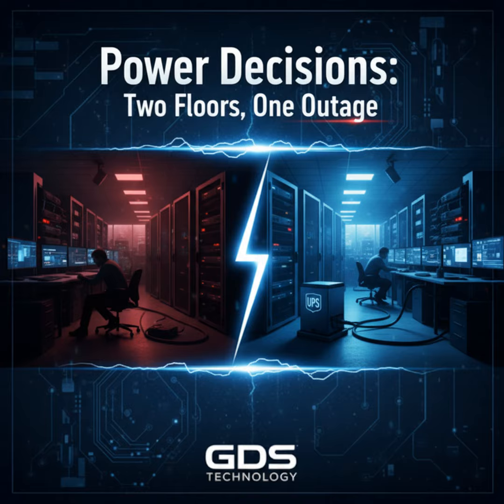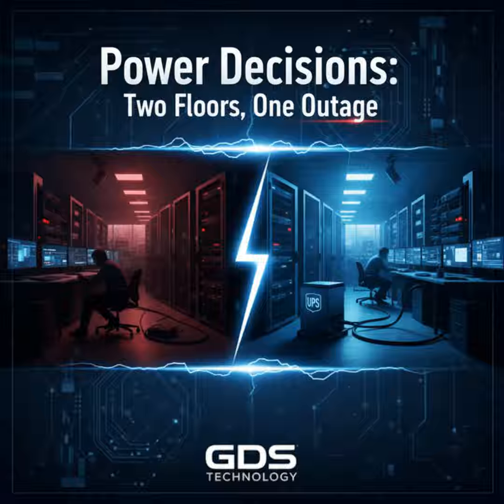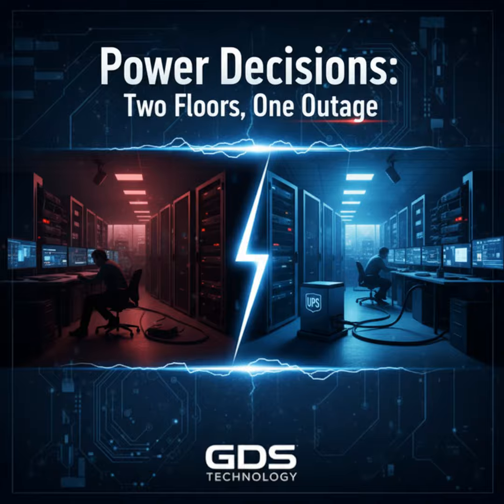What about centralized batteries versus distributed UPS modules? Centralized systems can be more efficient to monitor and maintain, and they simplify building-level control. Distributed UPS at tenant cabinets may be cheaper upfront and offer tenant-level isolation. Heuristic: if your building needs coordinated blackout tolerance for shared systems and you want a single pane of glass for monitoring, centralized makes coordination easier. If you expect high tenant churn and want isolation of responsibility, distributed might be better. Again, match the architecture to operational responsibilities and your staffing model.